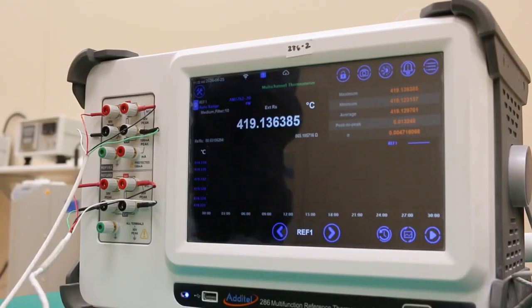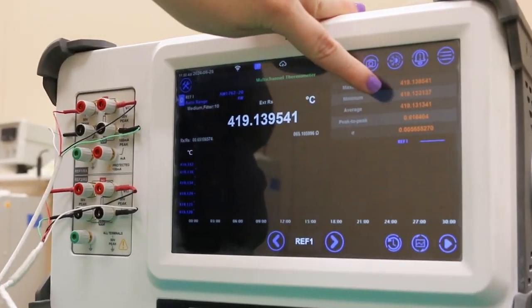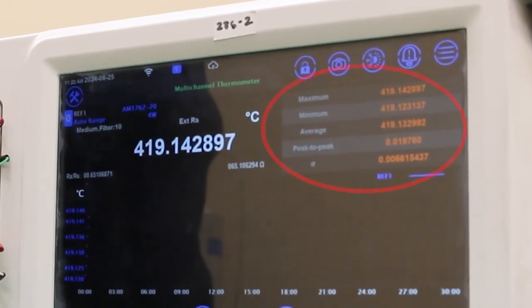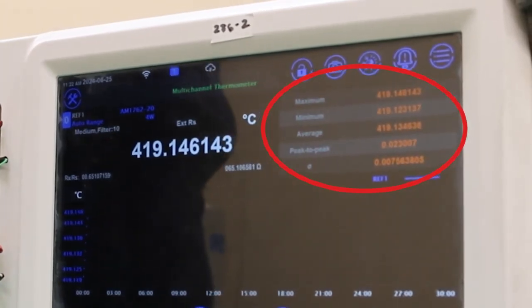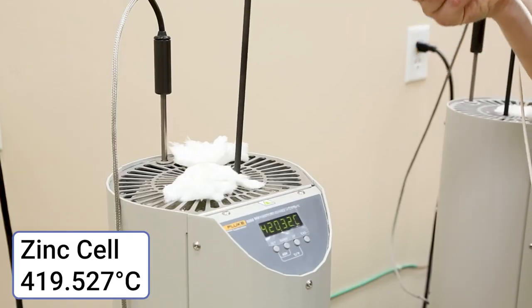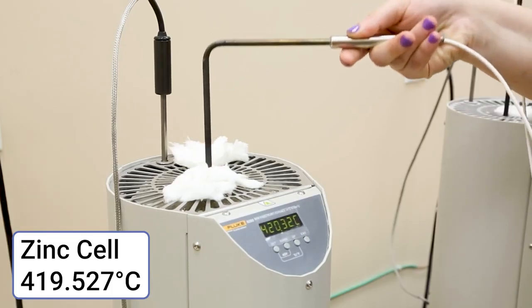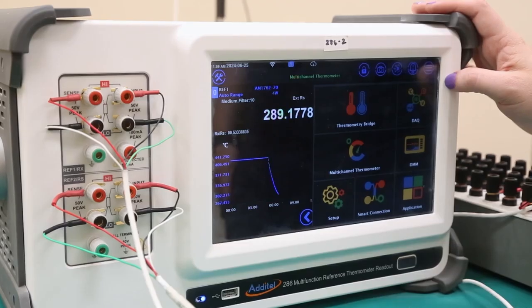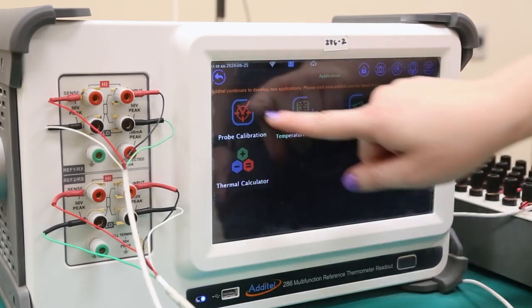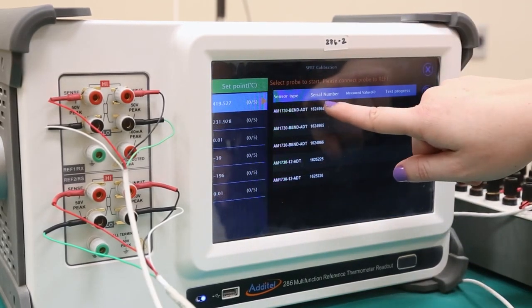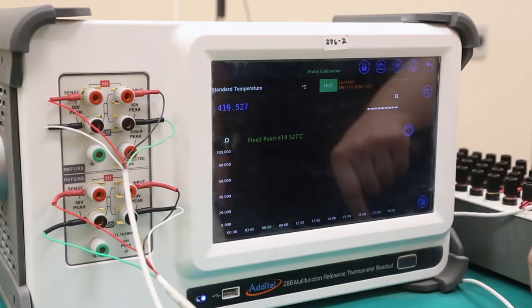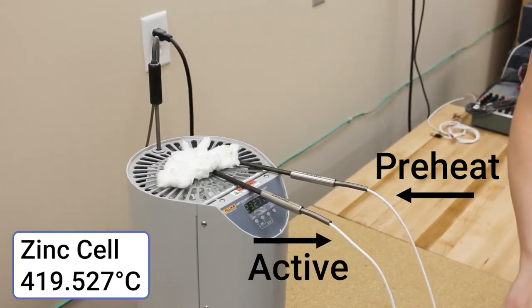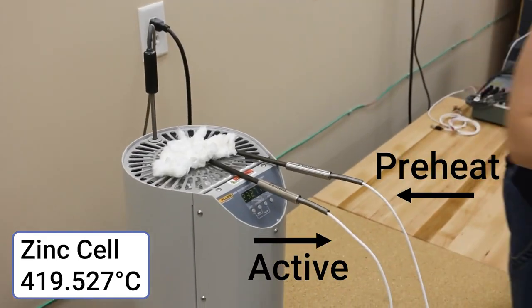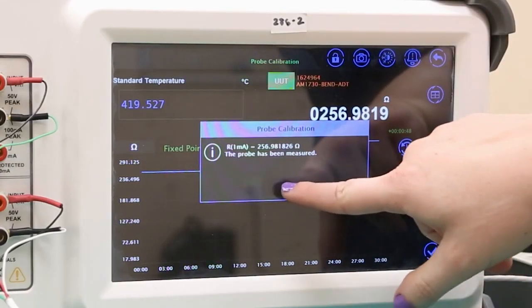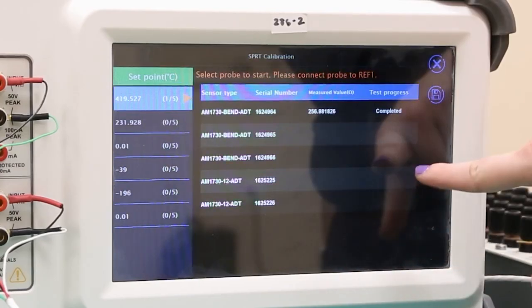the furnace. With the check standard, we can also see important stability statistics in the top right table, such as average temperature and peak-to-peak difference of the high and low temperatures. We can now remove the check standard and replace it with the DUT probe that was on standby. On the 286, we will go back to the probe calibration application, select our test, and select the first calibration point and probe that we are measuring. After the probe measurements begin, we can set up the next probe by adding it to the preheat well of the zinc cell furnace. Once the 286 has finished measuring the first probe, press the checkmark button to continue.